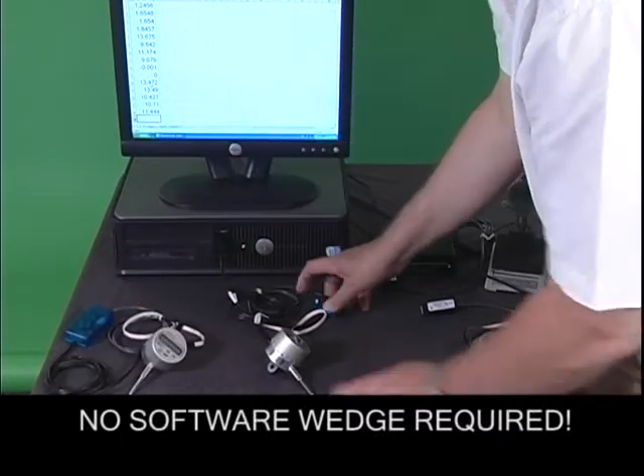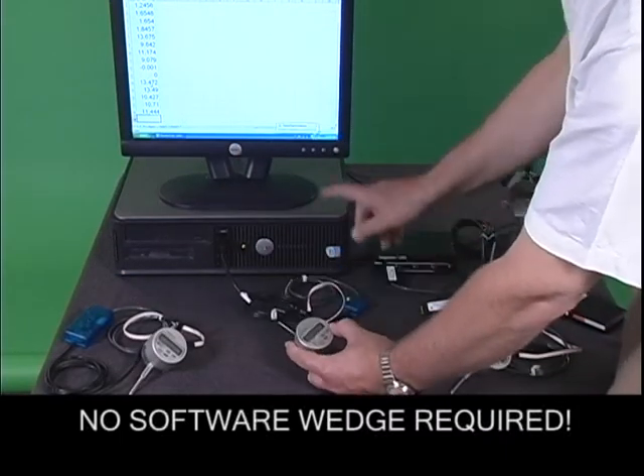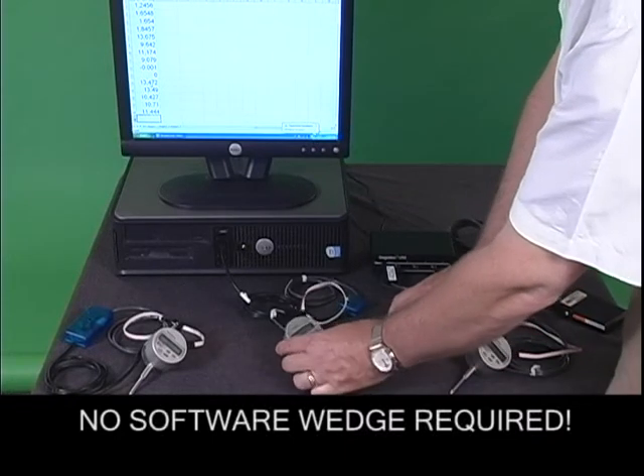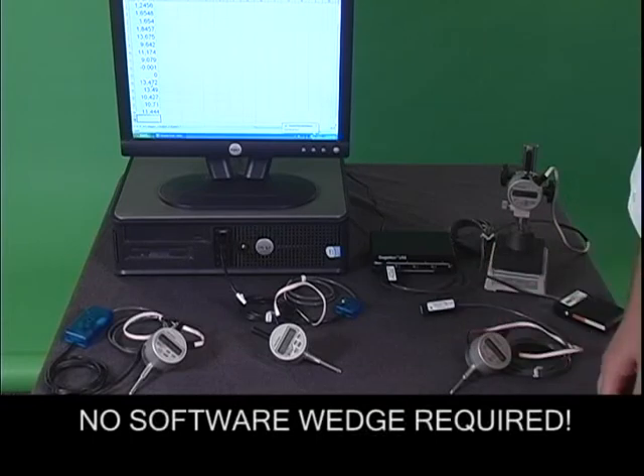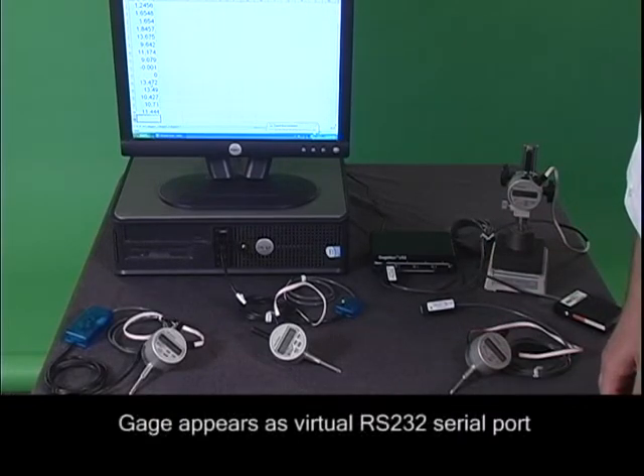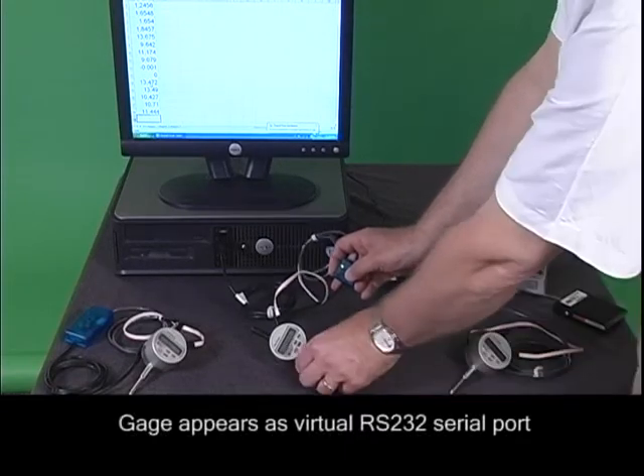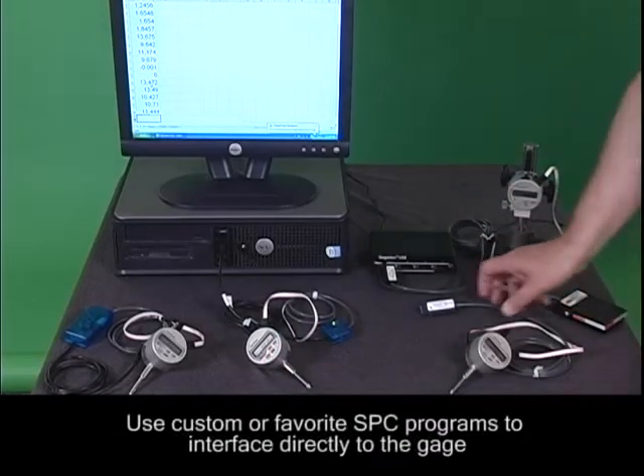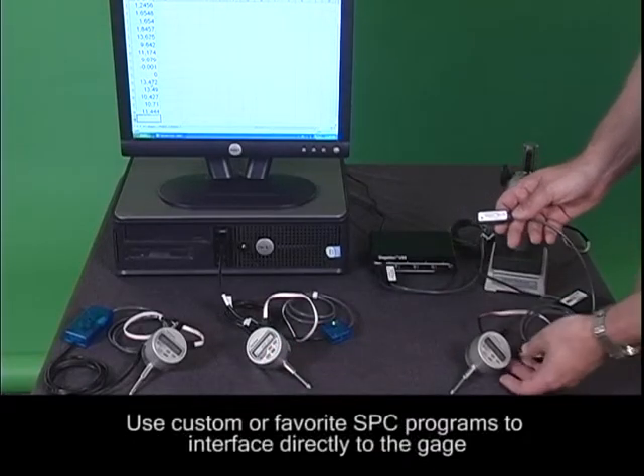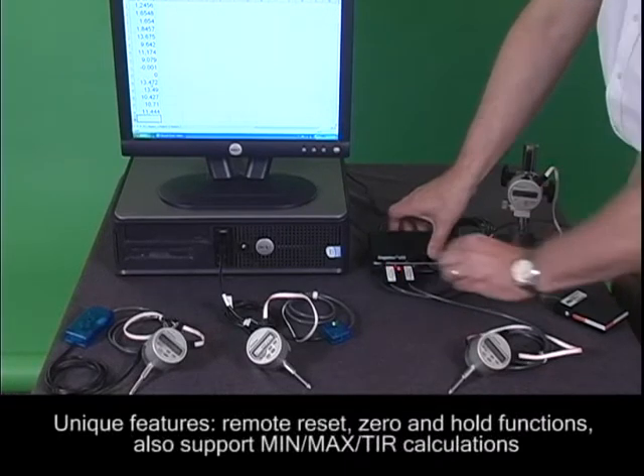We have also developed the smart cable USB for the Ono Sokki EG-225 that connects any single gauge to the PC's USB port. You can add more gauges as you need using off-the-shelf USB hubs. When you connect the EG225 to the USB port, we make the gauge appear as a virtual RS232 serial port. You can use your favorite SPC program or custom programs to interface directly to the gauge. One of the neat features we support is remote reset, zero and hold functions.